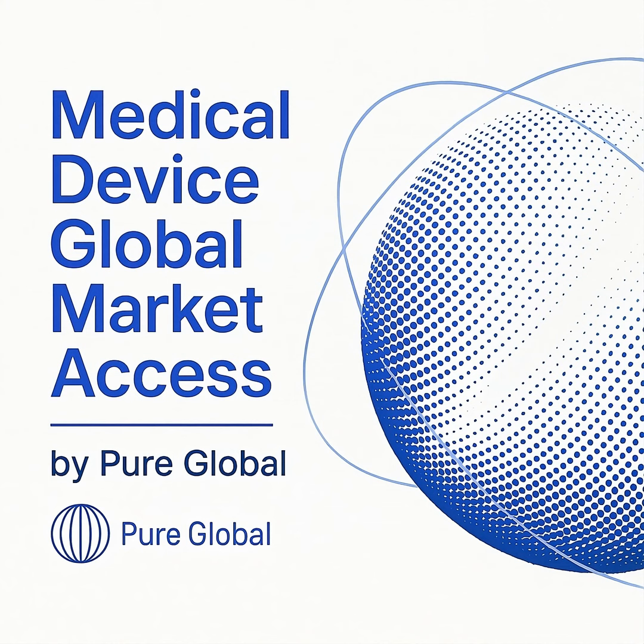For many devices, especially those that are higher risk, novel, or for which no clear equivalent exists, a formal clinical investigation will be required. A clinical investigation is a formal study or clinical trial involving human subjects designed to assess the safety or performance of a medical device. These investigations must be conducted in accordance with the requirements of the MDR, specifically Articles 62 through 81, and the principles of good clinical practice as outlined in the Harmonized Standard ISO 14155-2020. This ensures the ethical conduct of the study and the scientific validity of the data generated.